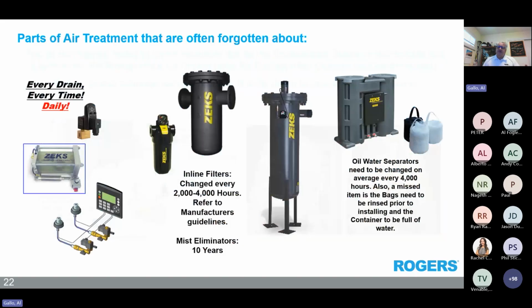Parts of the air treatment are often forgotten about. They just get put in and spaced out for whatever reason. They're in dark caverns. They get stuck in the corner. Drains. Drains are all over the place. If you think back to that very first picture I showed you, it had like seven drains: one for the compressor, the pre-filter, the dryer, the post-filter, the tank, and so on. There are a lot of drains on the system, and air treatment really isn't working unless you're getting the moisture out of the air system. It's the first line of defense.